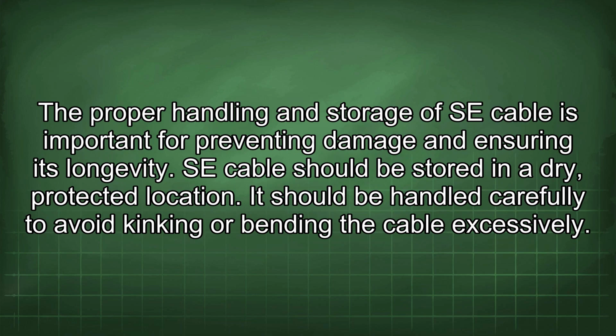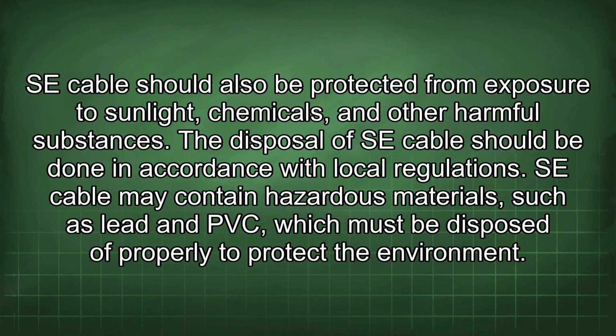The proper handling and storage of SE cable is important for preventing damage and ensuring its longevity. SE cable should be stored in a dry, protected location. It should be handled carefully to avoid kinking or bending the cable excessively. SE cable should also be protected from exposure to sunlight, chemicals, and other harmful substances.